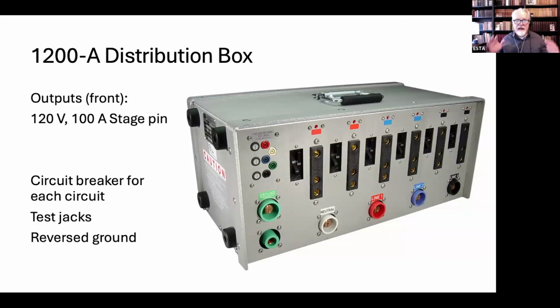So in order to make this magic happen, we have distribution boxes. And distribution boxes are where the feeders terminate. They terminate into these cam lock connectors along the bottom, right? There's your 5 wires. And you'll notice if you look along the top, there's color coding red, blue, and black to tell you that these 100 amp connectors are connected between neutral and red, blue, or black. So this is where you have your first reduction in cable size. Now we're stepping down from 4-aught cables down to just 100 amp cables, which are number 10 cable.